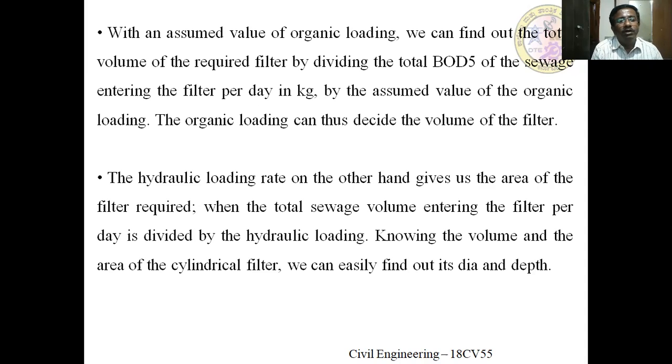Next, the hydraulic loading rate, on the other hand, gives the area of the filter required. It means the area of the filter also depends upon the hydraulic loading. The total sewage volume entering the filter per day is divided by the hydraulic loading. Knowing the volume and the area of the cylindrical filter, we can easily find out its diameter as well as depth. If it is circular, we find the total volume and fix the depth. Once you know the volume and the depth, it is possible to find the cross-sectional area of the filter media required.